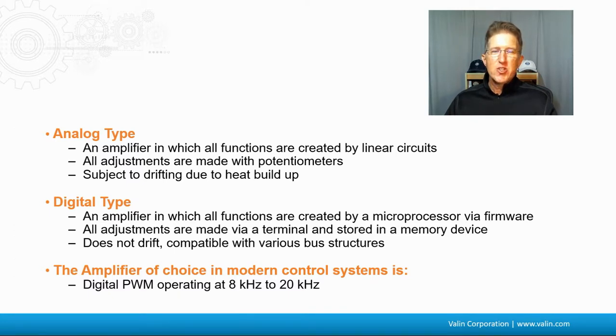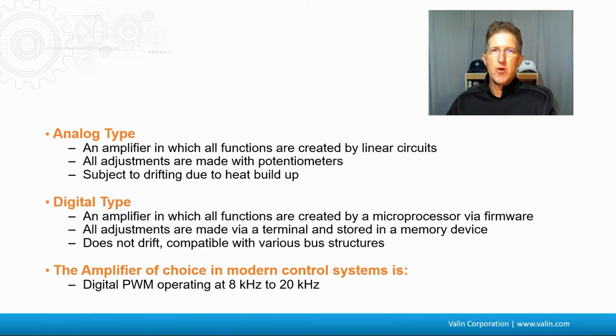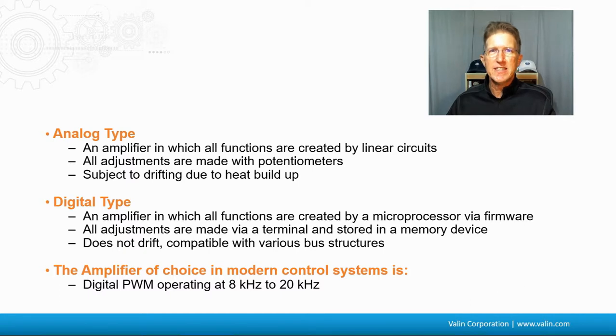Eight to 20 kilohertz is the typical chopping frequency for PWM. I've worked with drives up to 40 kilohertz, which are particularly needed for low inductance motors — we'll come back to that in just a second. Eight to 20 kilohertz is very typical; I've also seen 4 and 16, but those are the typical ranges.